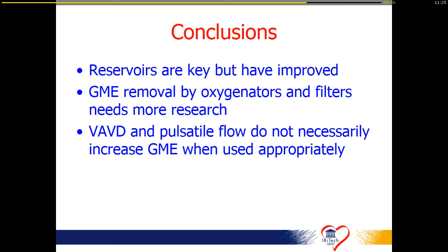We do know that GME removal by oxygenators and filters exists, and that it exists at certain levels. But we need more research to see what is the best combination of having good mass transfer and good GME removal, but at the same time not at the expense of hemocompatibility, because that's another important issue in our older population today. And then finally, the good news is when you use VAVD and pulsatile flow or VAVD alone, and you work according to the known standards, it does not necessarily mean that you increase the risk for GME generation in the patient. Thank you very much for your attention.